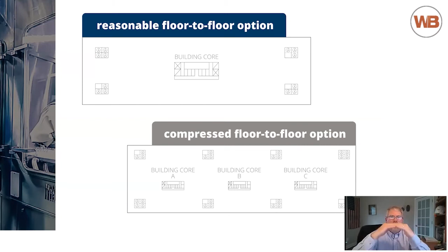When you get to a compressed floor to floor, on the bottom, you can see how with additional money and equipment you could create a strategy to add additional cores. You could add an A and B core and centralize those, or add three cores - A, B, C - and decentralize, making the exhaust ducts even smaller to feed each zone or half of a floor instead of each floor. You end up with smaller risers, which means smaller horizontal laterals coming out of the shafts.